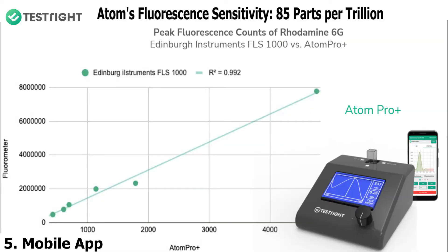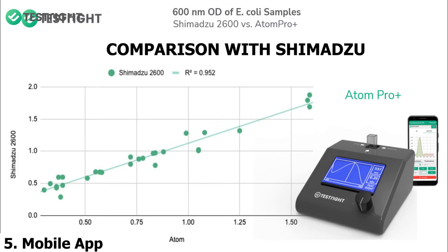Thus we saw how Atom can be used for absorbance, fluorescence, and reflectance — all three in a single package. Its fluorescence sensitivity is down to 85 ppt (parts per trillion) for rhodamine B dye. Its absorbance is compared against international brands like Shimadzu, and the results have been published on screen, showing very good linearity.